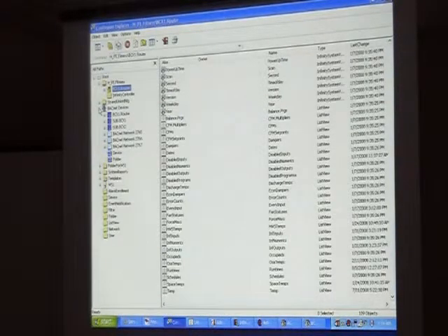The number one thing to remember, especially when you go to troubleshooting, is the BACnet side is the only side that it really exists in. The database itself, the communications, all the information is really BACnet information. It's not Infinity information. The programming translates BACnet information and gives you a view of it on the Infinity side. But the Infinity side is easier to get around in, it's easier to see. That's what we use for our displays and our graphics and all that kind of stuff. So that's what we always use.